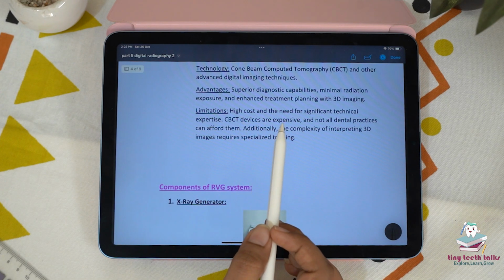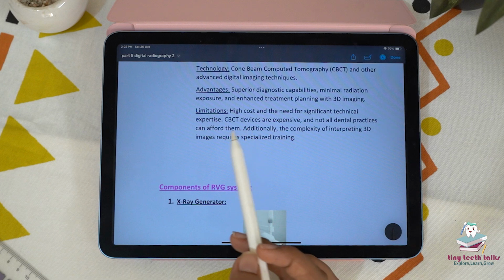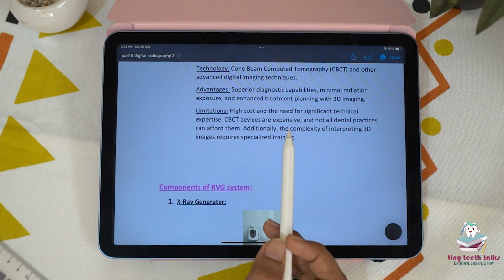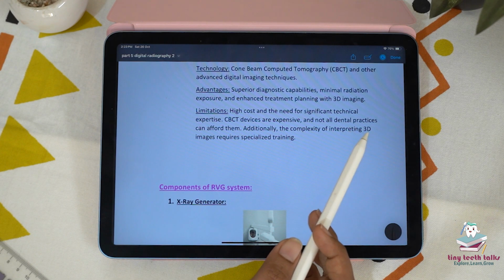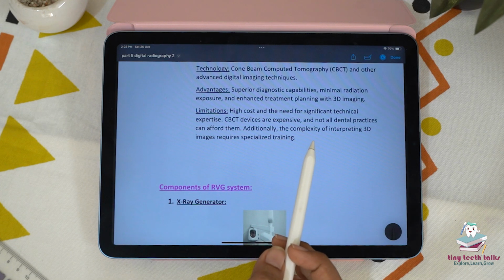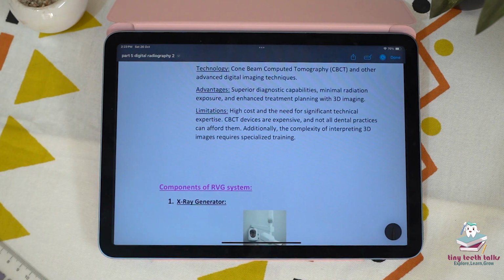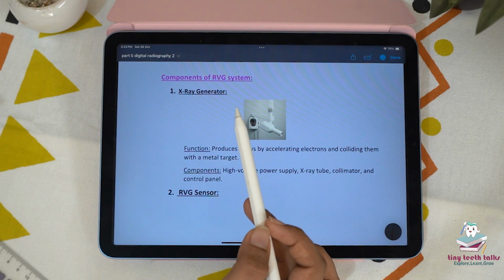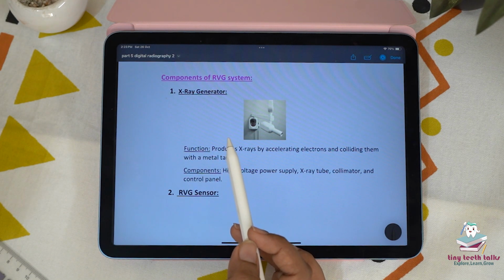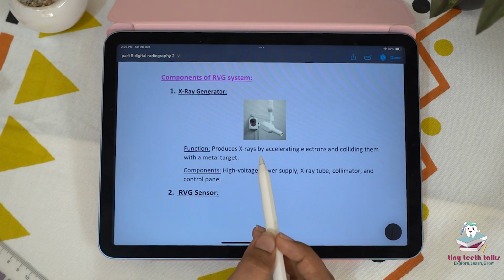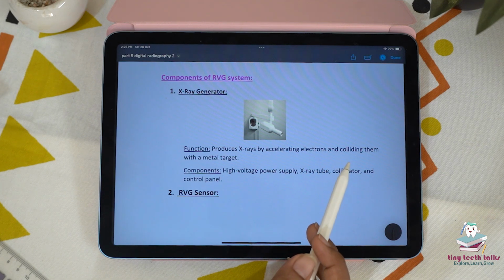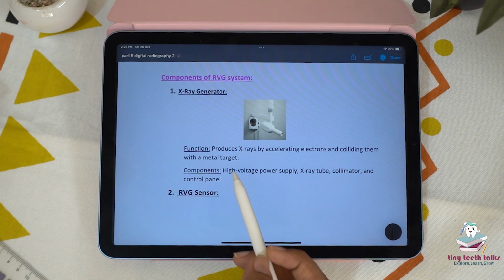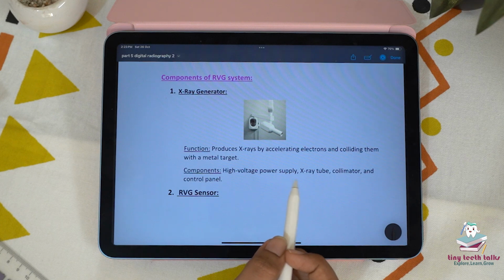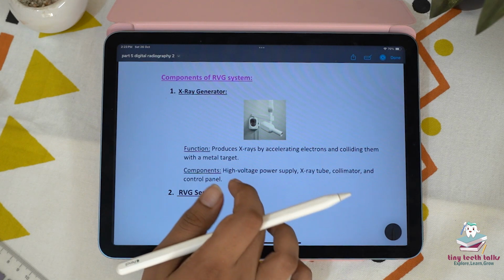Limitations are high cost and the need for significant technical expertise. CBCT devices are expensive and not all practices can afford them. Additionally, the complexity of interpreting 3D images requires specialized training. Coming to the components of the RVG system, the first is the X-ray generator. The function is to produce X-rays by accelerating electrons and colliding them with a metal target. Components: high voltage power supply, X-ray tube, collimator, and control panel.